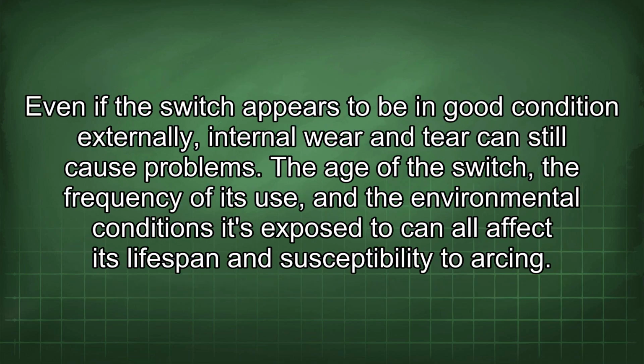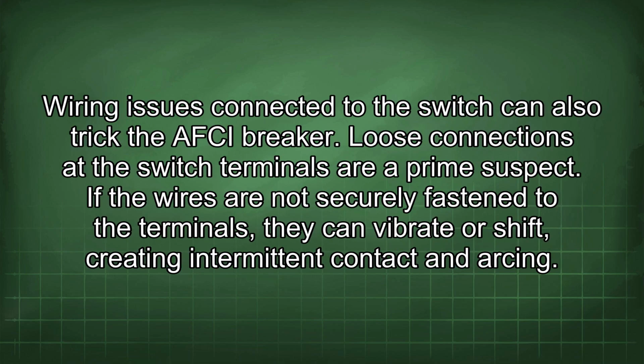Even if the switch appears to be in good condition externally, internal wear and tear can still cause problems. The age of the switch, the frequency of its use, and the environmental conditions it's exposed to can all affect its lifespan and susceptibility to arcing. Wiring issues connected to the switch can also trip the AFCI breaker. Loose connections at the switch terminals are a prime suspect. If the wires are not securely fastened to the terminals, they can vibrate or shift, creating intermittent contact and arcing.